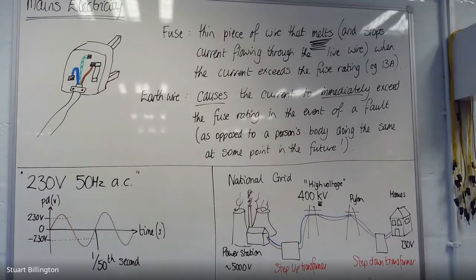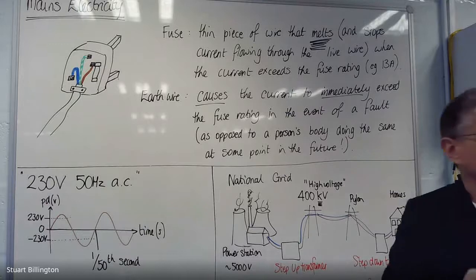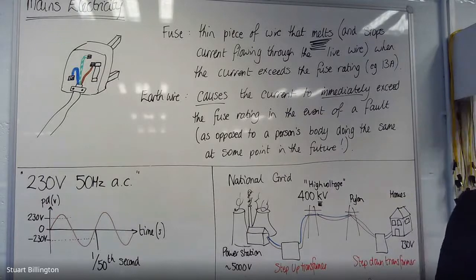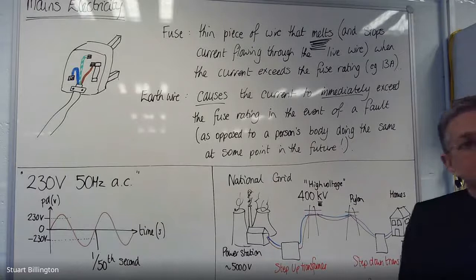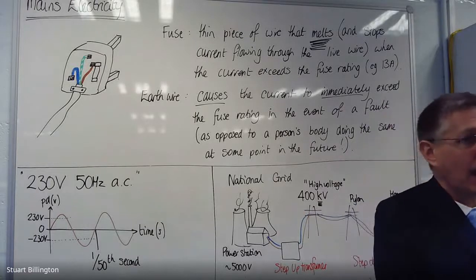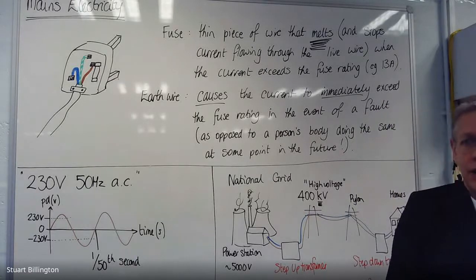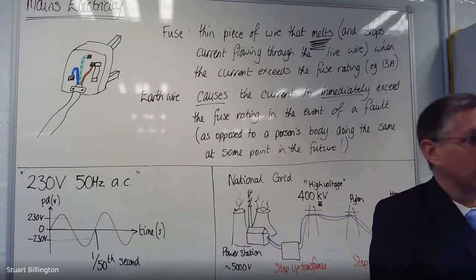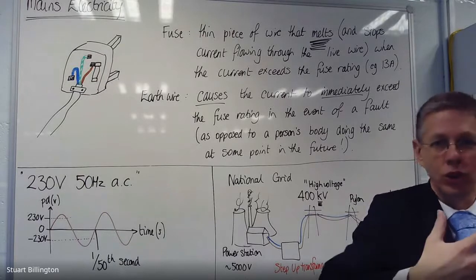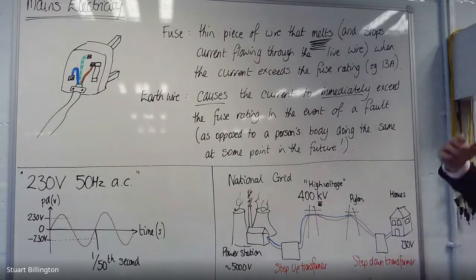So why might the current go too high? Well, in a bad example, the current might go too high because you've just put a knife inside a toaster and there's a load of current flowing through you, electrocuting you. That would be bad. However, that's not what the fuse is primarily for, because it takes half a second or so to melt, and you can easily get a lethal electric shock during that half second.